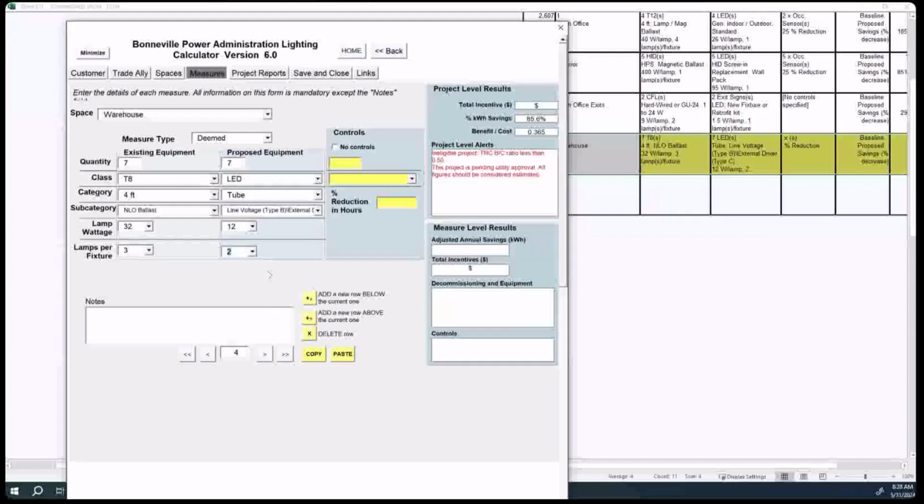So if I'm going to de-lamp a 4 lamp fixture, I'll tend to want to bump the wattage up on the LED replacement depending on what's needed. I mean, if it's overlit already with the existing, say, 4 lamp T12, and you can go with a 2 lamp T8 LED tube, then go for it. But you might need to do a mock-up to make sure it's going to meet the application needs.